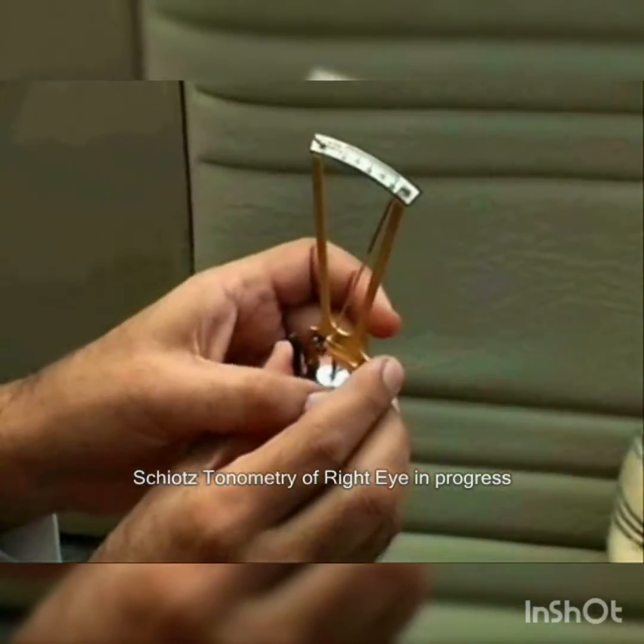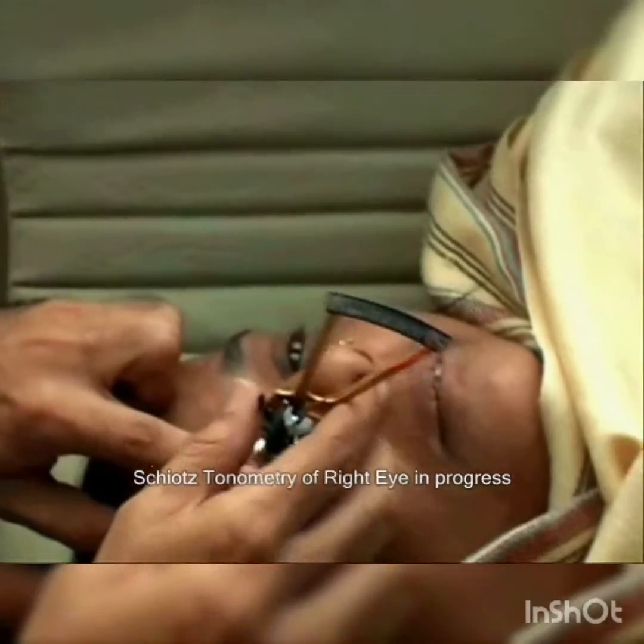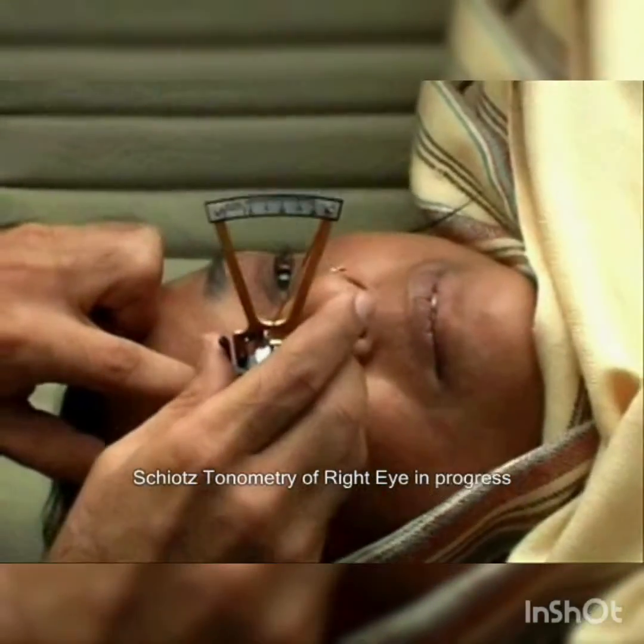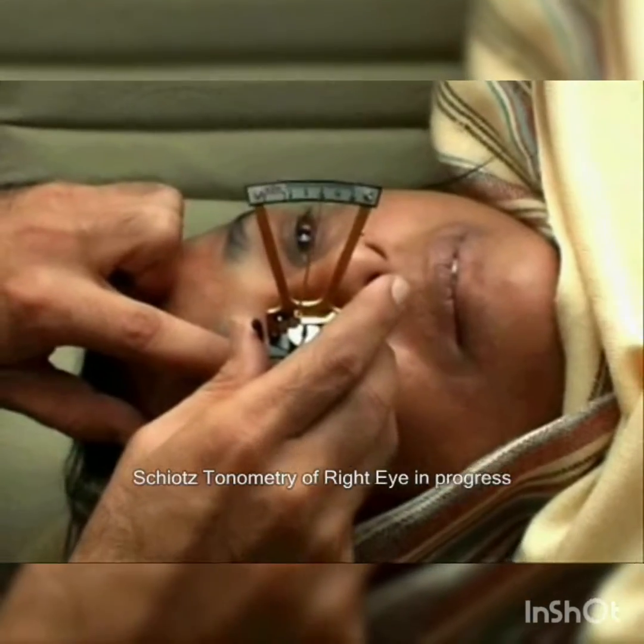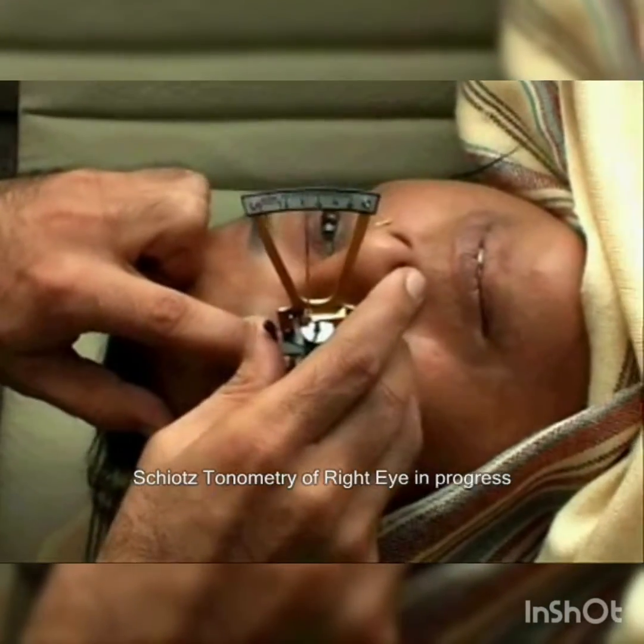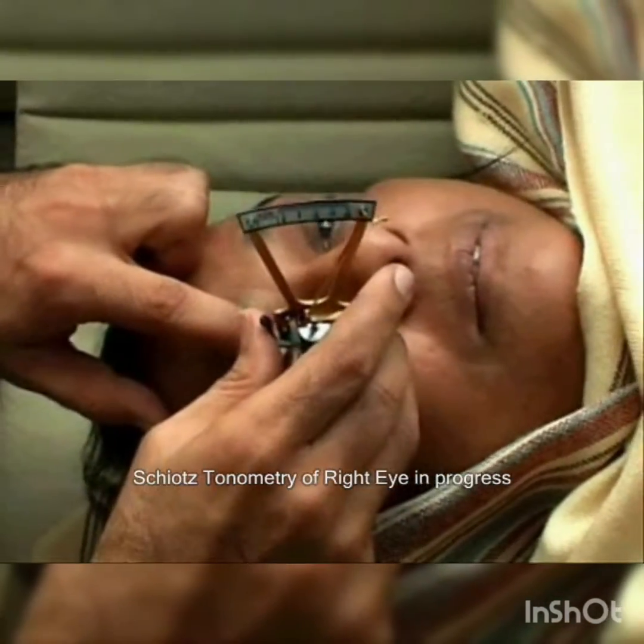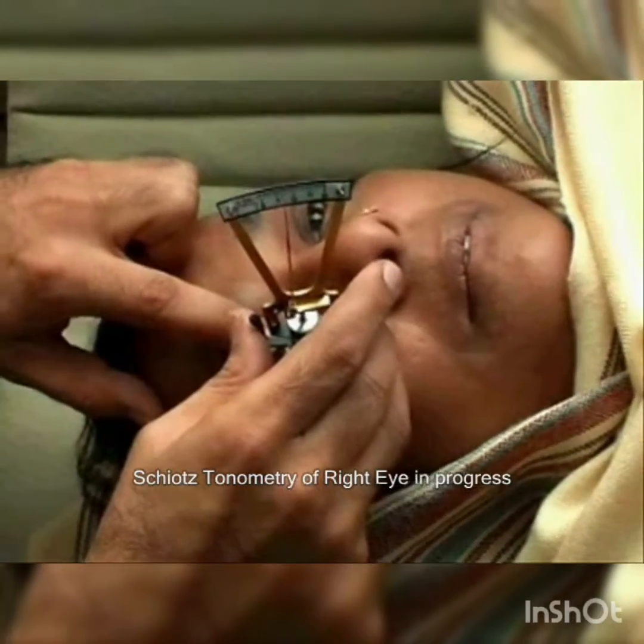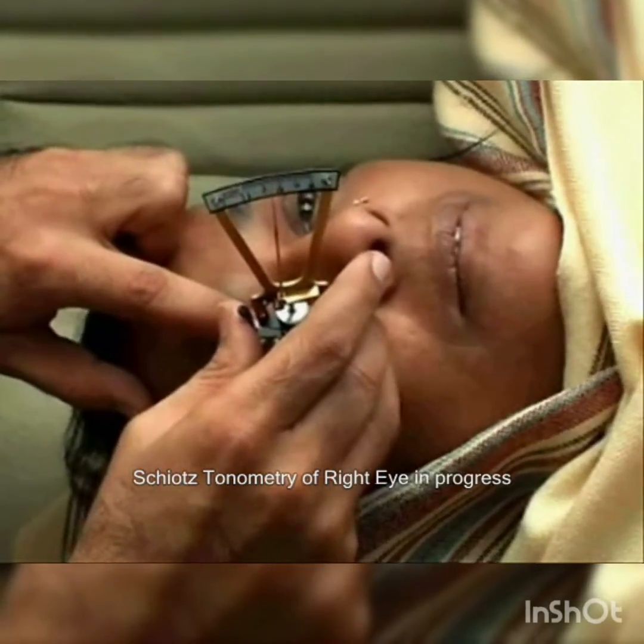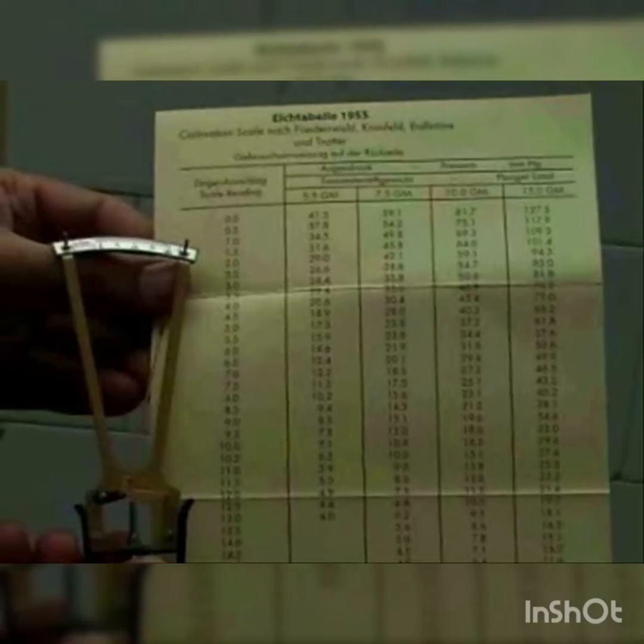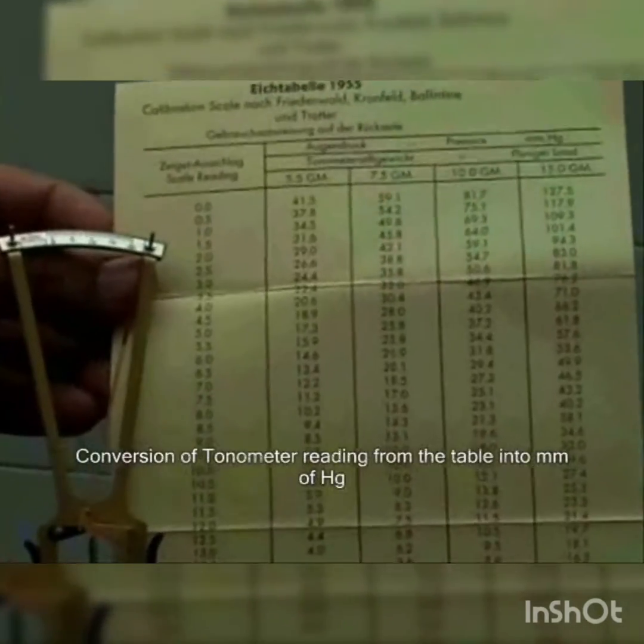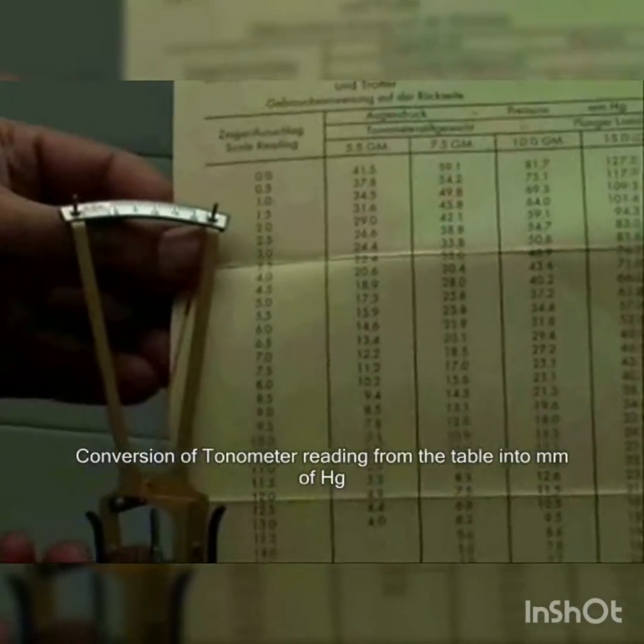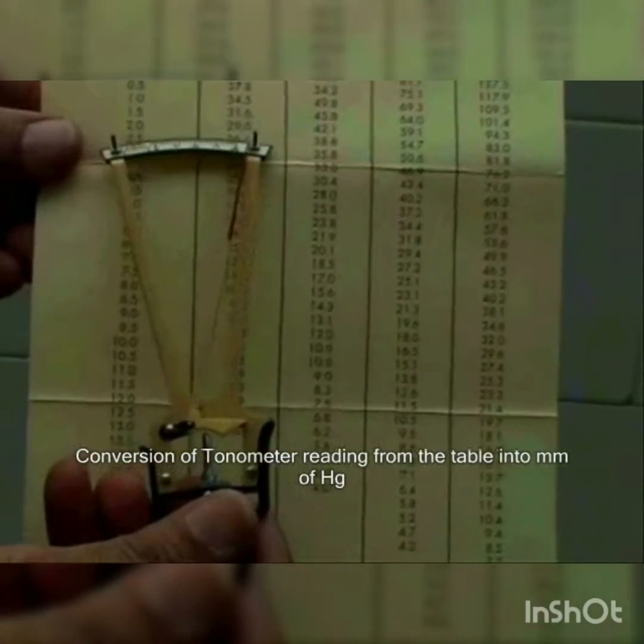Either eye is checked, and in case of higher intraocular pressure, additional weights are added to the plunger and readings are checked. The amount of indentation on the instrument is read on the table chart in millimeters of mercury.